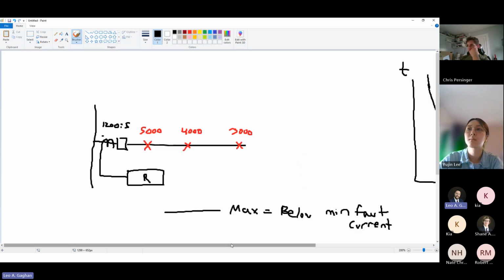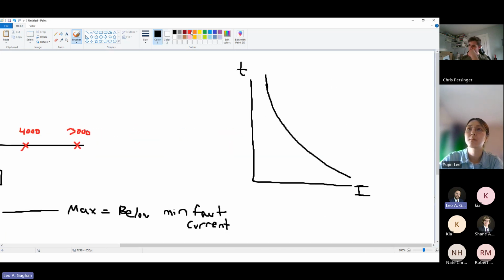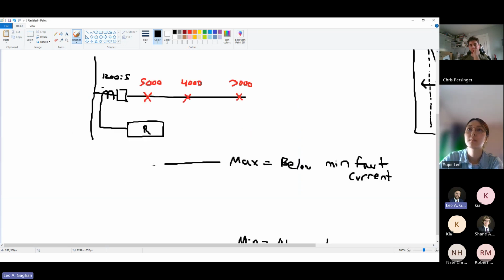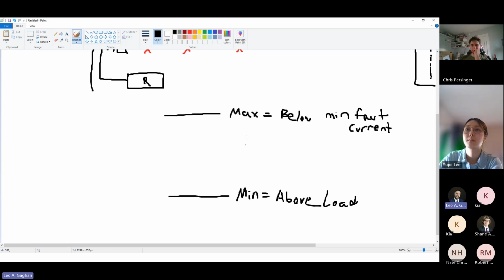And a pickup relates to where you start your curve here. So as you increase and decrease your pickup, what happens is this curve moves left and right, essentially. That's the pickup. We'll move it left and right. So you've got to figure out what your min and max allowable pickups are. That's really your first goal.